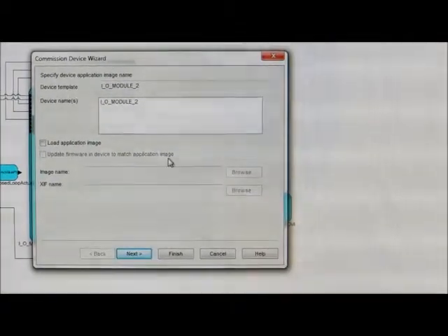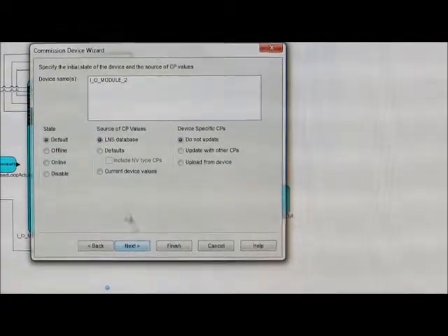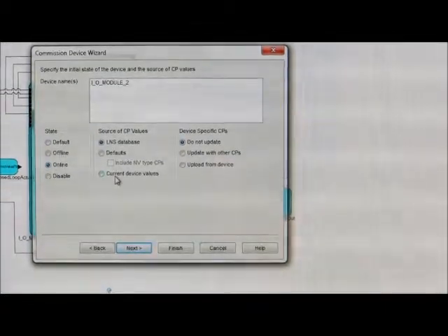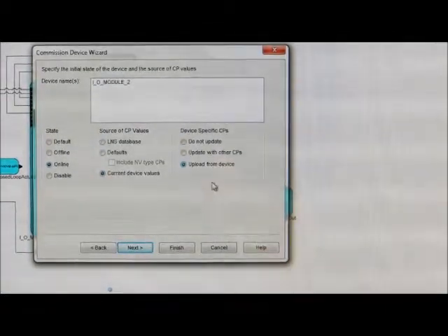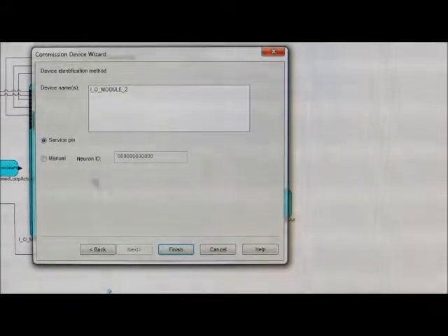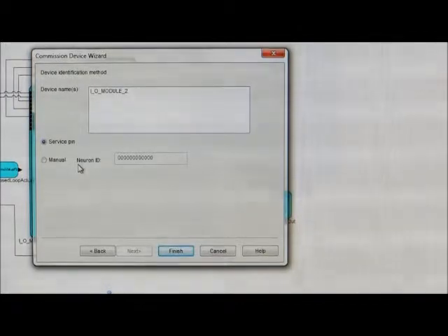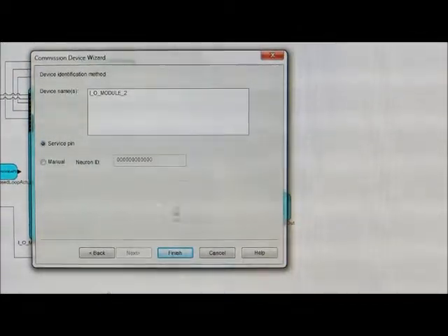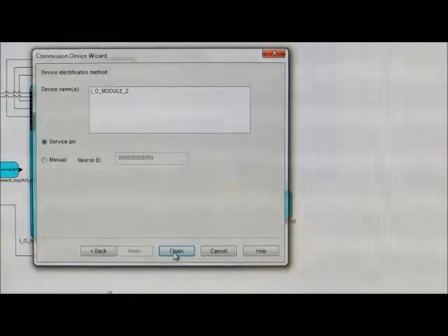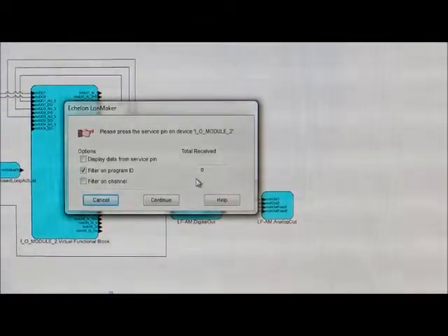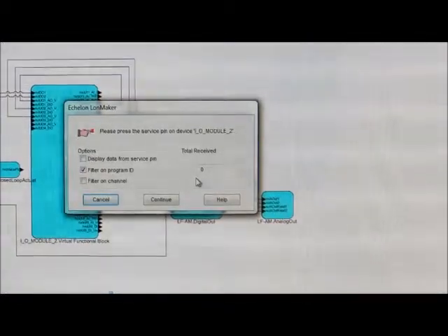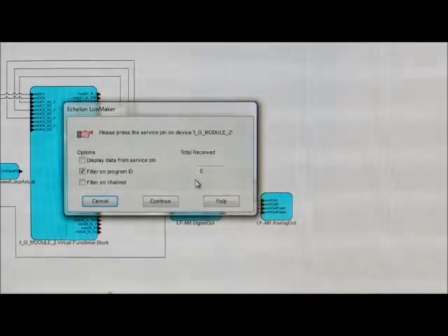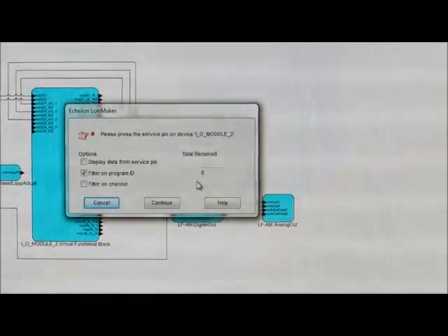It'll show you which device you're going to commission. Hit next. We're going to go online, current device values, upload from device. Click next. And we're going to use the service pin to enter the Neuron ID into the system. So click the service pin and click finish. And then it'll ask you to hit this service pin on the device. So in the previous video you saw where the service pins were on each of the devices. So we're on IO Module 2. We'll hit the service pin on the lower left-hand corner and it'll commission the device to the network.